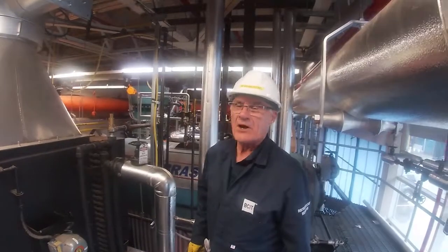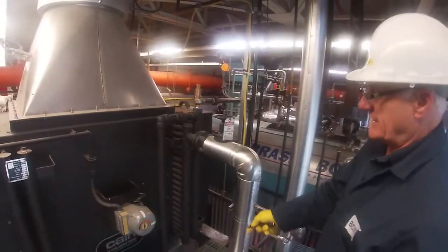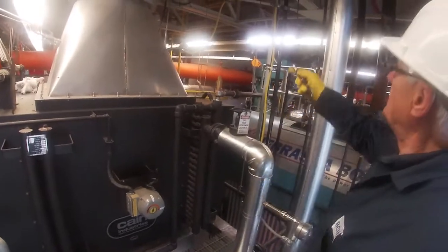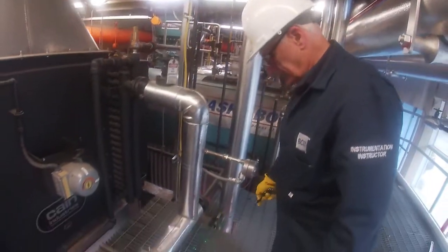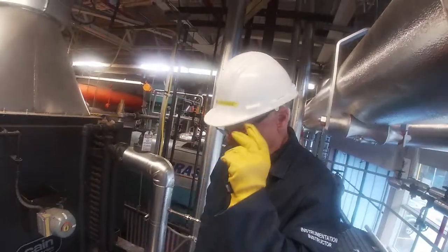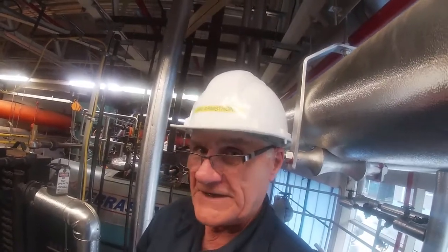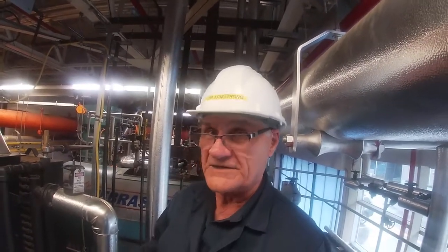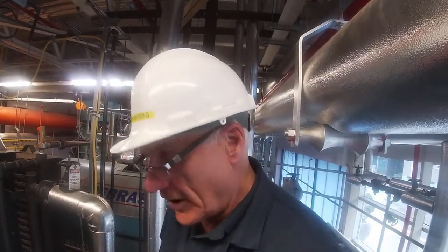Okay, we're up on the deck. Behind me here, or just in front of me, is the economizer itself. The feed water is coming in on this line up here and drops down like so. Goes down, and down below us is the feed water valve. And that's important. The feed water valve is on the upstream side of the economizer. If it's on the downstream side of the economizer, the feed water valve gets subjected to extremely high temperatures, and I've seen them fail. So to be installed properly, they should be on the upstream side of the economizer.